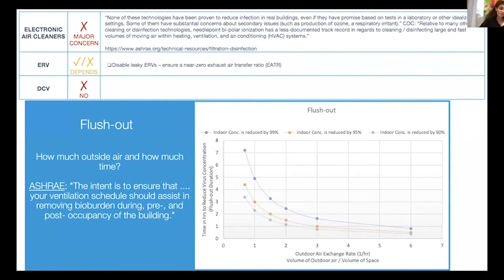Demand control ventilation, no, because here the idea is that you don't want to change your outside air on demand. You want to ask, how many people are returning to my building? As Dr. Shada mentioned before me, you calculate the minimum outside air for the number of people that are returning and you set it constant. You don't need to vary it.